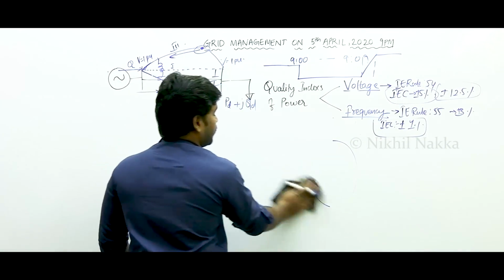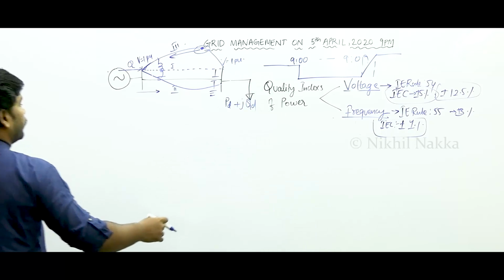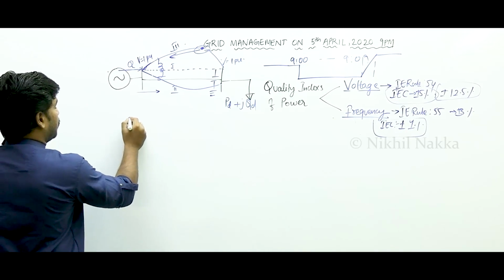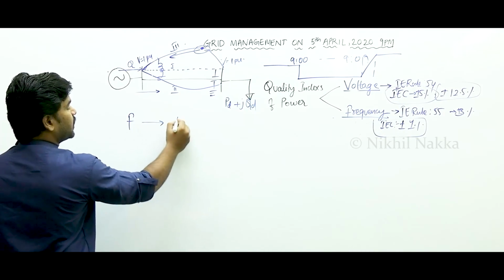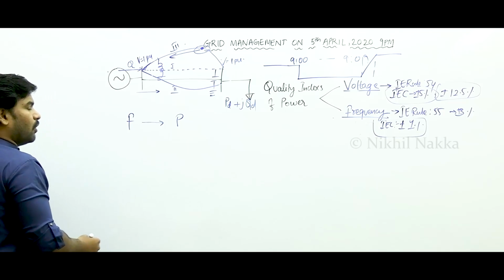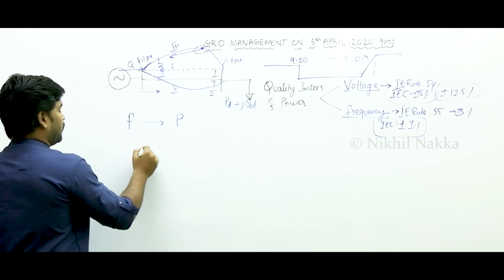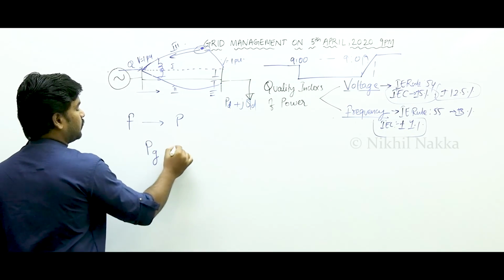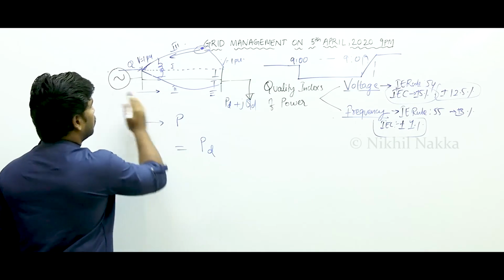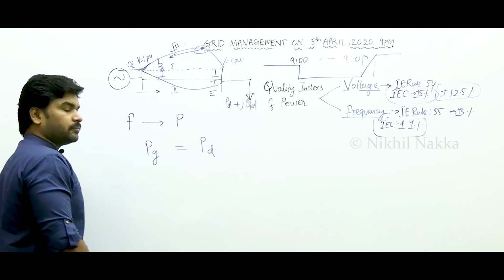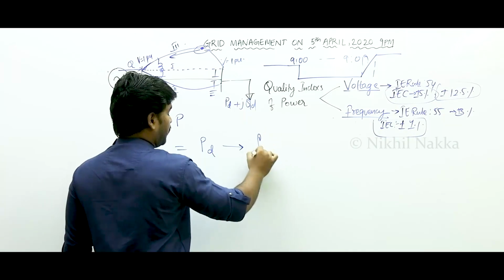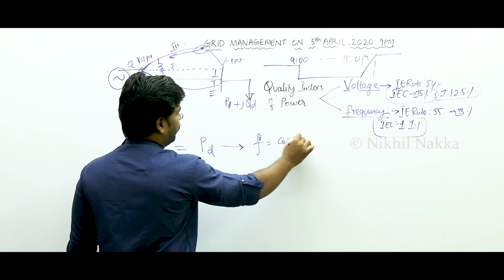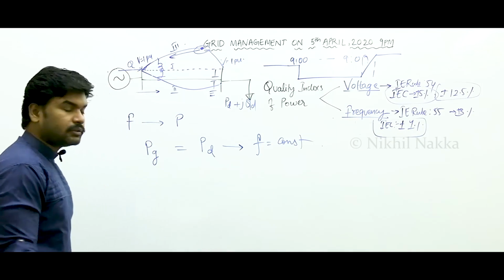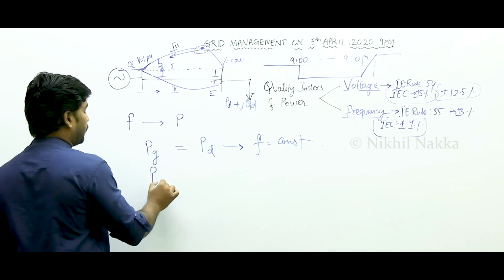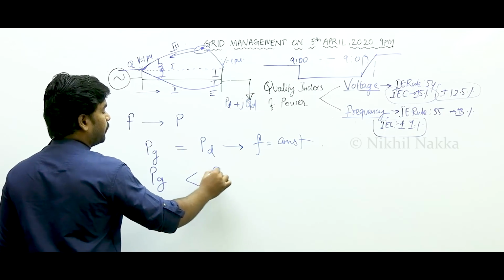Now I will get into frequency management. According to this principle of decoupling, the frequency component depends upon active power mismatch. What do I mean by active power mismatch? Active power generated is equal to active power demand - how much generated, that much demand, no problem, frequency remains constant at the rated frequency. Now consider active power generation is less than active power demand.